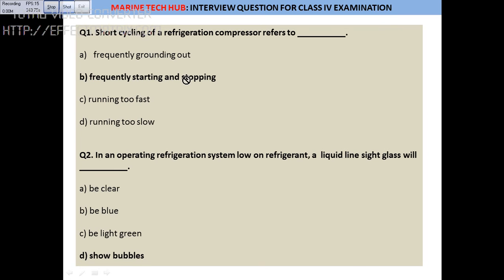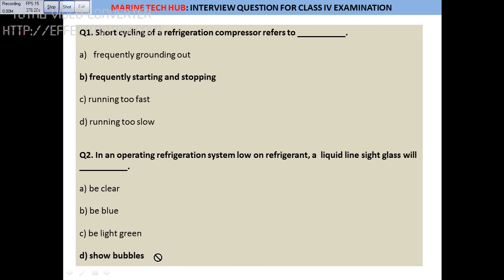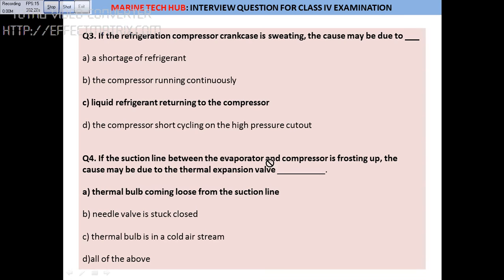Question 2: In an operating refrigerant system with low refrigerant, what will we see in the sight glass? You will see bubbles coming. If there are bubbles in the sight glass, that means the refrigerant liquid level is low. This can be observed during inspection — if you see bubbles, you need to charge the system, as there is likely a leakage.